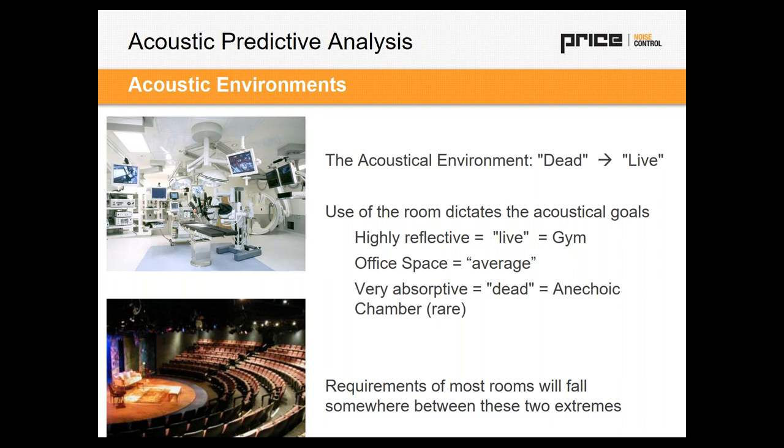Some of the things you'll need to remember from yesterday's webinar is some of the terminology, such as understanding your acoustical environment. You're going to hear a lot of terminology such as live. It is a live room, so a gymnasium or an operating room. Very hard surfaces, few people, nothing absorbing sound. Most of the occupied spaces, such as offices, for example, or open offices, are going to be average. So that's another term you need to remember. And it could be absorptive or medium dead. You will not see a dead environment unless it is an anechoic chamber. So it is pretty rare.